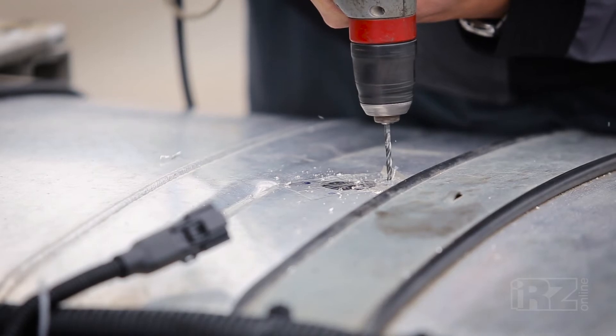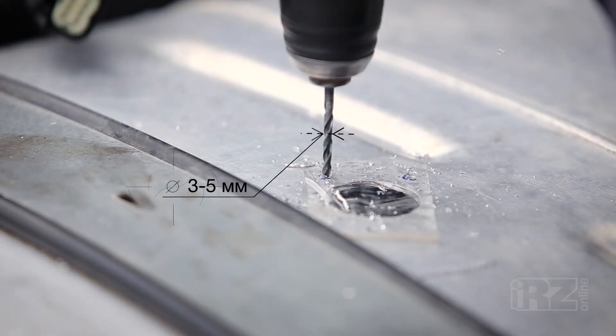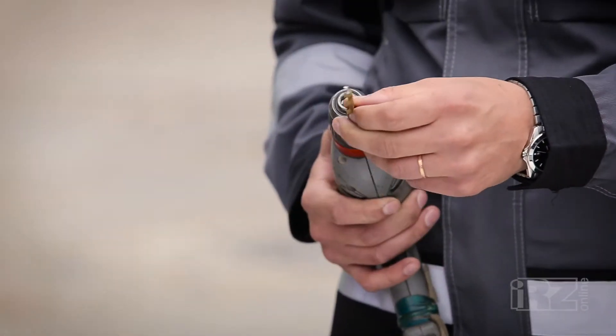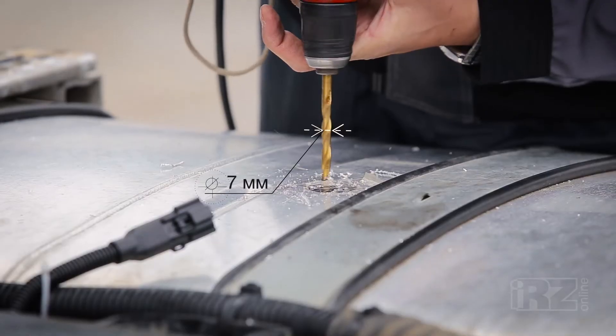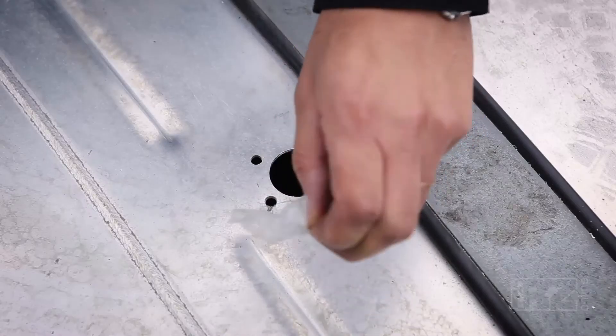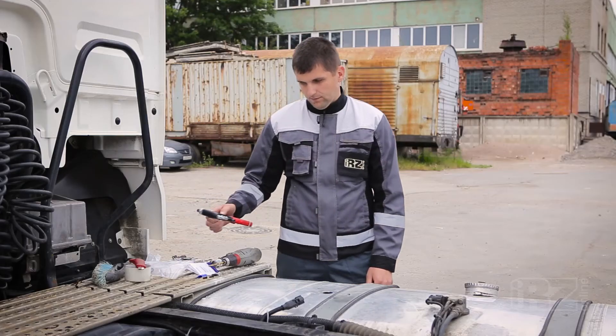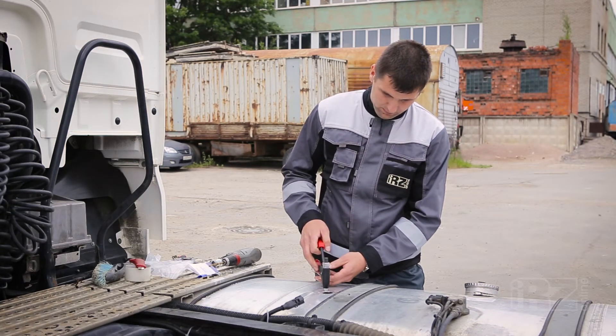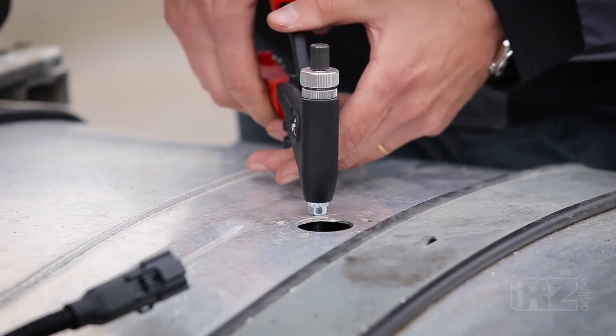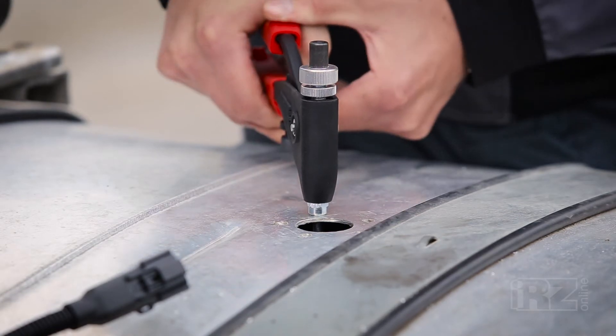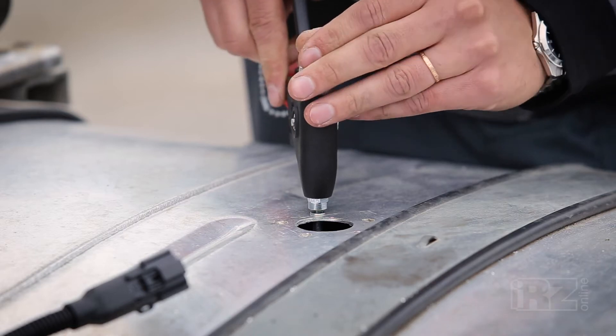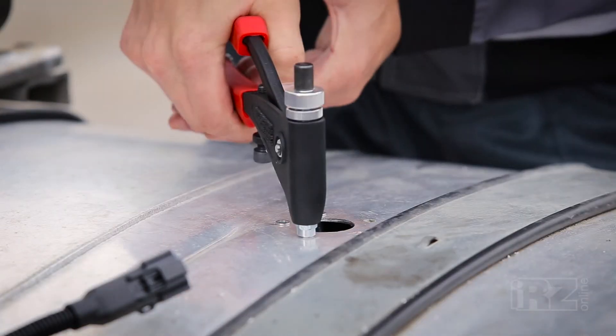Previously marked holes should be bored by a thin drill with diameter of 3 to 5 mm, then use a drill diameter of 7 mm. Fit the stack bolts into the prepared holes using the riveter. The bolt should be screwed on the full length of the threaded rod. In general, the bolt should be completely perpendicular to the plate of the sensor and the wall of the tank. Then you need to rivet out the stack bolt and remove the threaded rod.